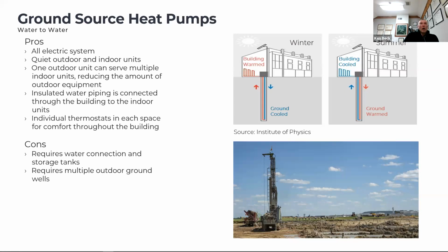So this is water to water heat pumps. We circulate the water through the ground to pre-cool or preheat it, and we send that to a heat pump that either heats the water or cools the water and sends it to fan coils within the building. The heat pumps themselves would be in a mechanical room. They would not be in the building space. So the compressor is not within the occupied building. Again, very quiet system once you're out in the building.